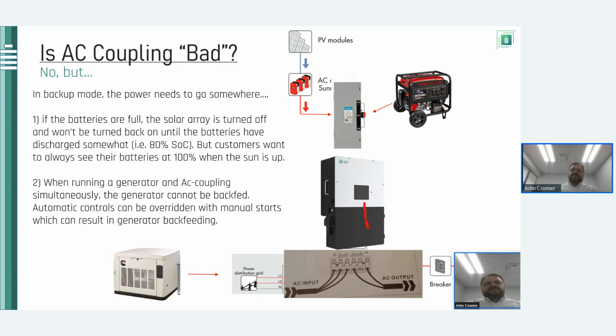So this is very much an edge case circumstance, but when you sell thousands of batteries, you will interact with people who encounter those edge cases. And you say, okay, well, the grid side of the inverter definitely has black start capability, because when I haven't installed my battery yet, I can still just do solar only, and even if I haven't installed solar yet, I connect the grid and I can turn the inverter on and it turns on. So I know that the grid side can turn the inverter on by itself. And so I'm just going to connect the generator to the grid side of the inverter. And that's fine. That's a valid configuration.